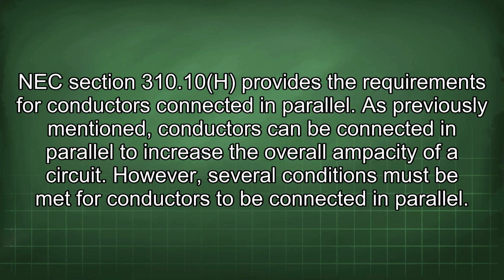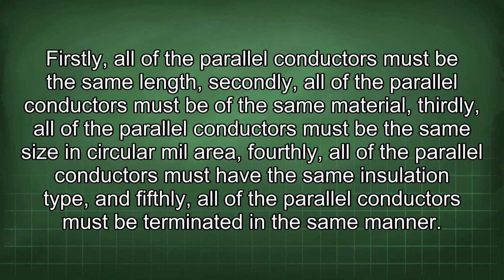NEC section 310.10(H) provides the requirements for conductors connected in parallel. As previously mentioned, conductors can be connected in parallel to increase the overall ampacity of a circuit. However, several conditions must be met. Firstly, all of the parallel conductors must be the same length. Secondly, all of the parallel conductors must be of the same material. Thirdly, all of the parallel conductors must be the same size in circular mil area. Fourthly, all of the parallel conductors must have the same insulation type. And fifthly, all of the parallel conductors must be terminated in the same manner.